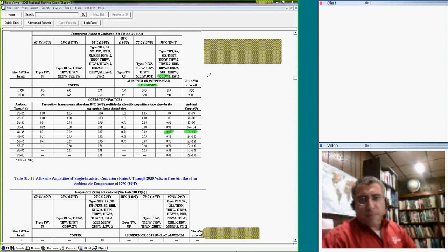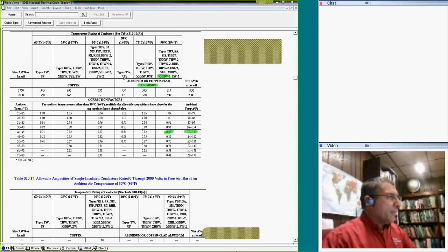The derating factor, because of the conductor, is 0.87. Now, my friend Matthew said, Chad, I don't like this type of insulation that you're using, and I'm going to use XHHW in a wet location. Look at that, guys, XHHW in the two locations. If you use it in a wet location, it's 75. If you use it in a dry location, it's 90. So if you use XHHW in a wet location, my derating factor is 0.82. My friend Eric said, I don't like what you guys have picked, I love TW and I can't live without it. I'm going to use TW insulation. His derating factor is 0.71. Can you see that, based on the insulation, you come up with a different derating factor?